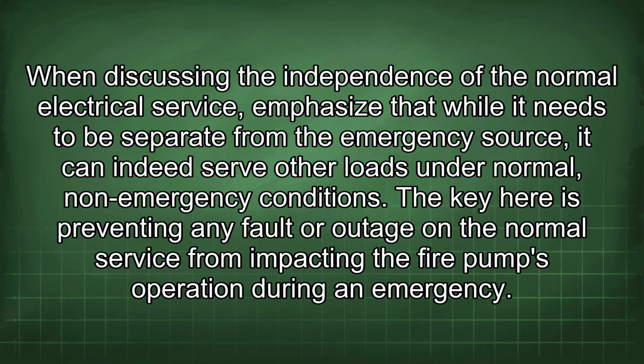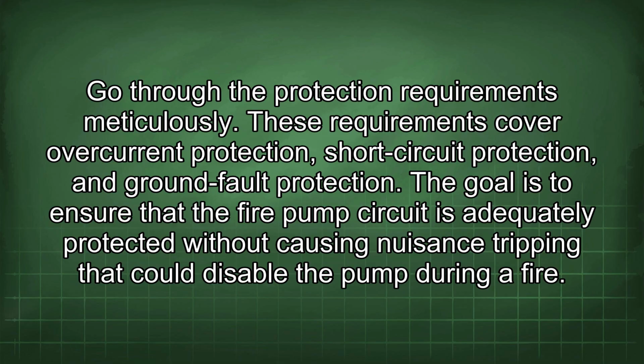When discussing the independence of the normal electrical service, emphasize that while it needs to be separate from the emergency source, it can indeed serve other loads under normal, non-emergency conditions. The key here is preventing any fault or outage on the normal service from impacting the fire pump's operation during an emergency. Go through the protection requirements meticulously. These requirements cover overcurrent protection, short-circuit protection, and ground fault protection. The goal is to ensure that the fire pump circuit is adequately protected without causing nuisance tripping that could disable the pump during a fire.